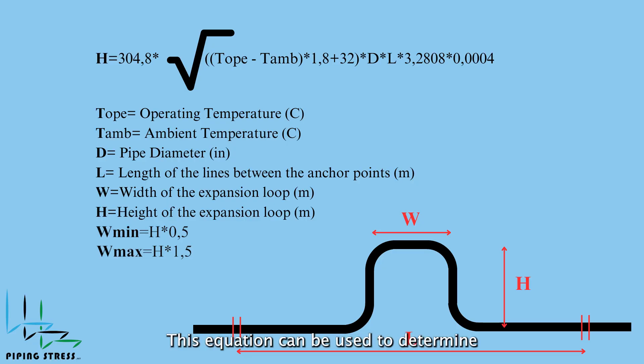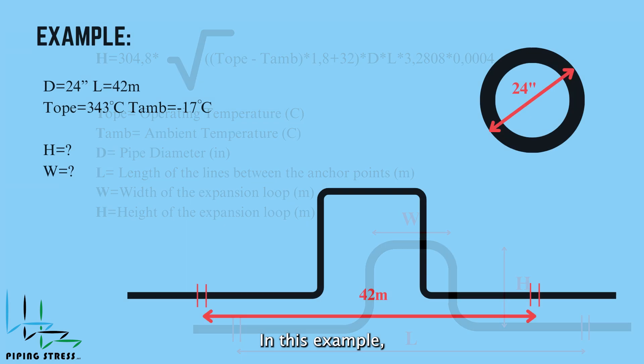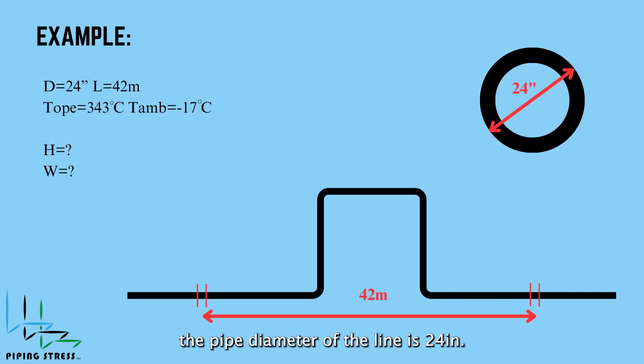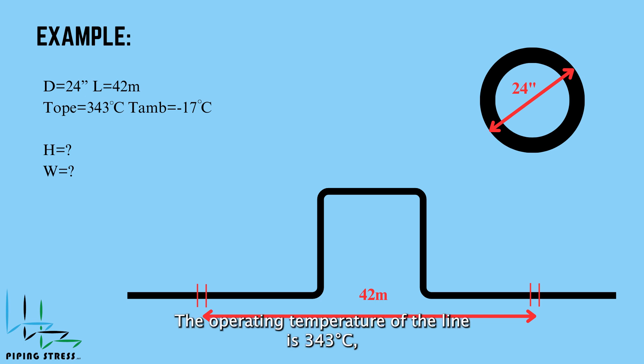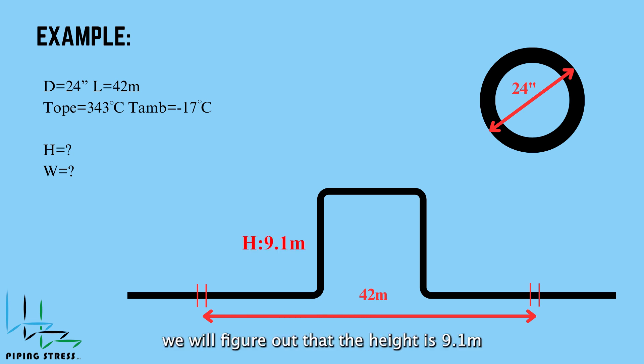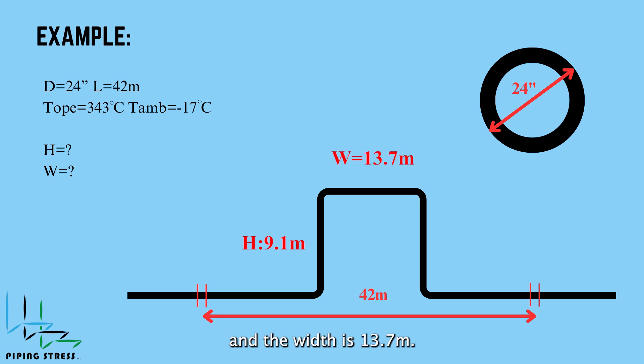This equation can be used to determine the size of the expansion loop. In this example, the pipe diameter is 24 inches and the length is 42 meters. The operating temperature is 343 degrees Celsius and the ambient temperature is minus 17 degrees Celsius. Once we apply these figures in the formula, we find that the height is 9.1 meters and the width is 13.7 meters.